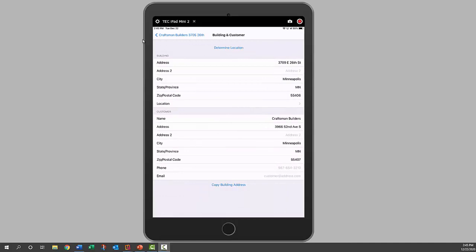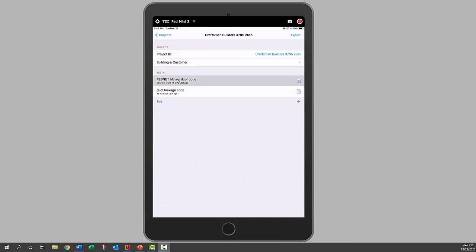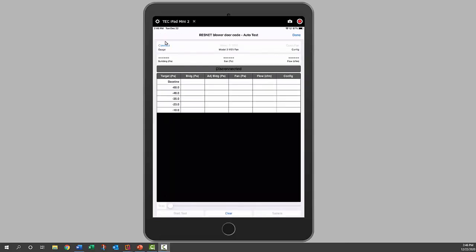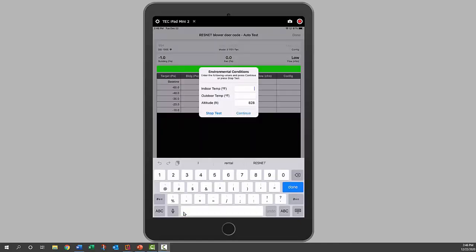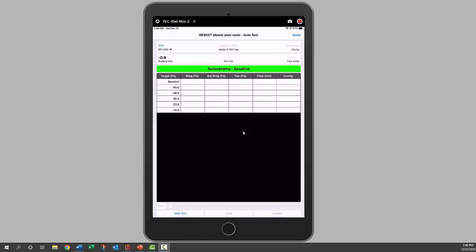We'll go back one more time and now we're going to do a blower door test. So we'll click on that one. We've got our volume entered in here already. We're going to depressurize the house. Three air changes per hour is our target, so we will choose run test and connect to our gauge. Idle monitoring, so we're ready to start our test. Click start test. We'll enter in our indoor and outdoor temps. It brought in our altitude, so go continue.